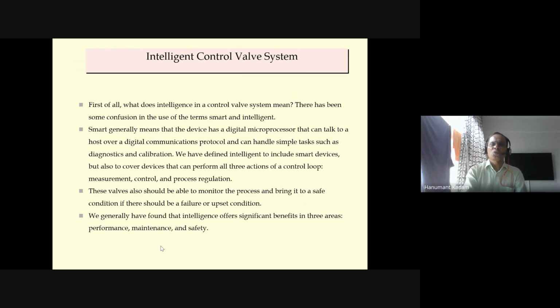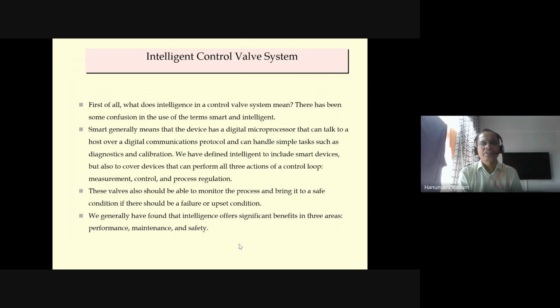So, intelligent control valve system. First of all, what does intelligent in a control valve system mean? There has been some confusion in the use of the terms smart and intelligent. Smart generally means the device has a digital microprocessor that can talk to a host over a digital communication protocol and can handle simple tasks such as diagnostics and calibration. We have defined intelligent to include smart devices, but also to cover a device that can perform all three actions of a control loop: measurement, control, and process regulation.